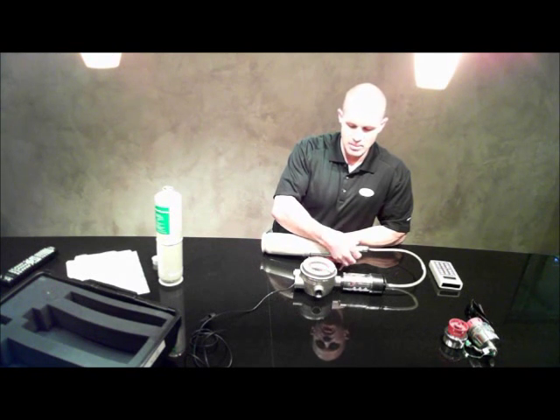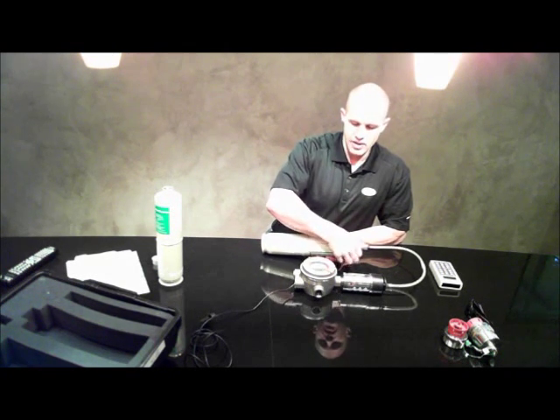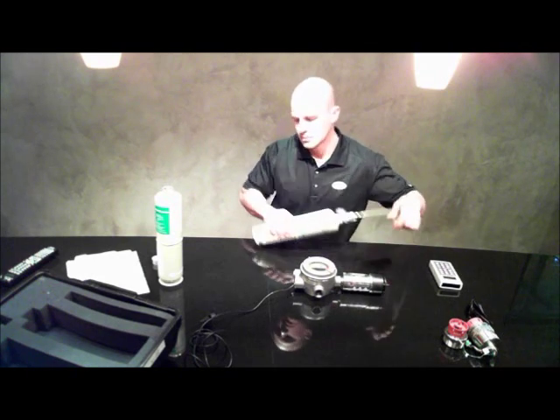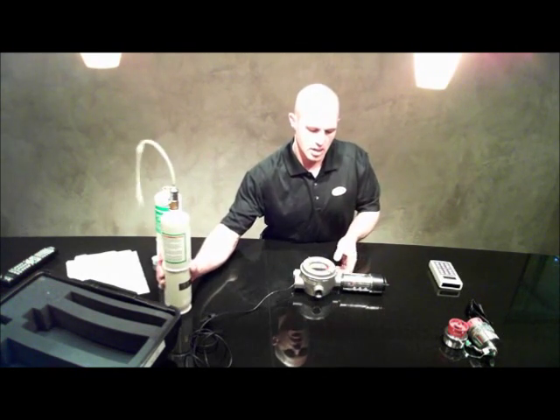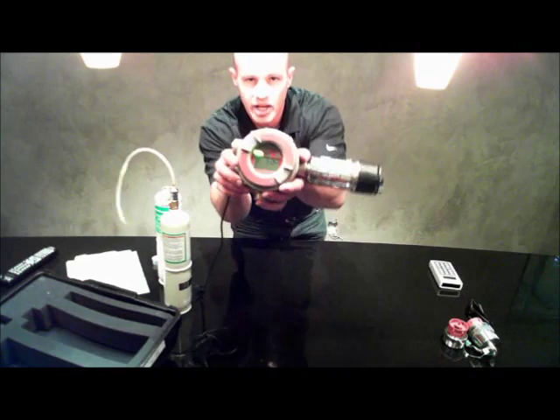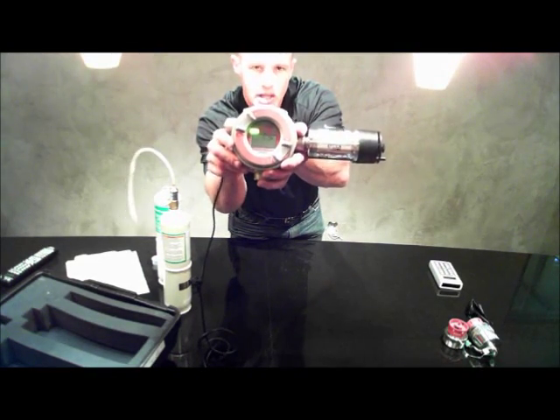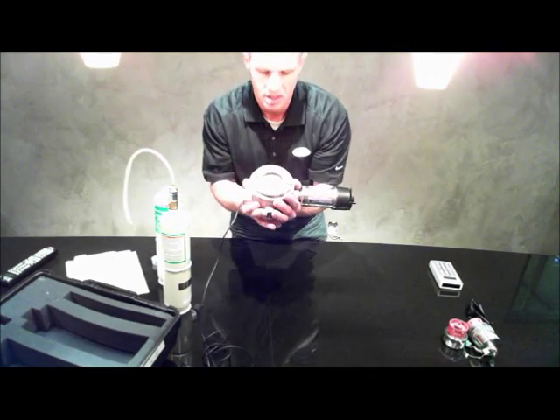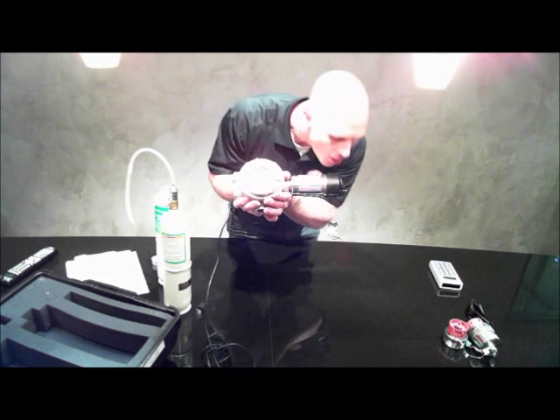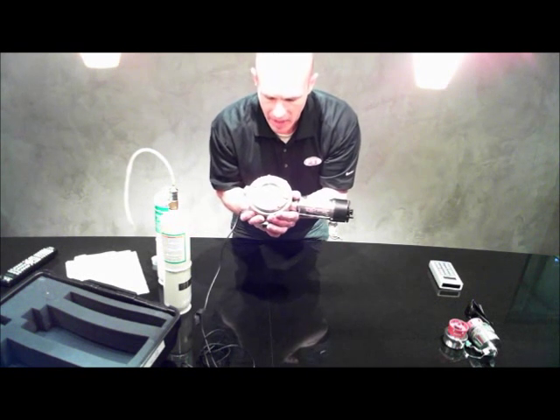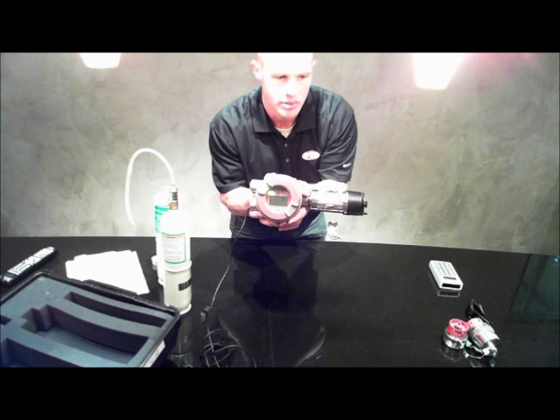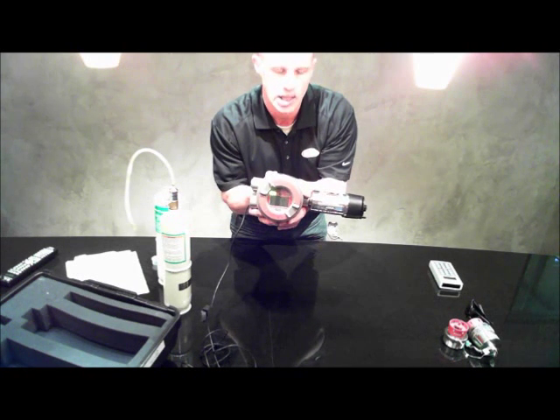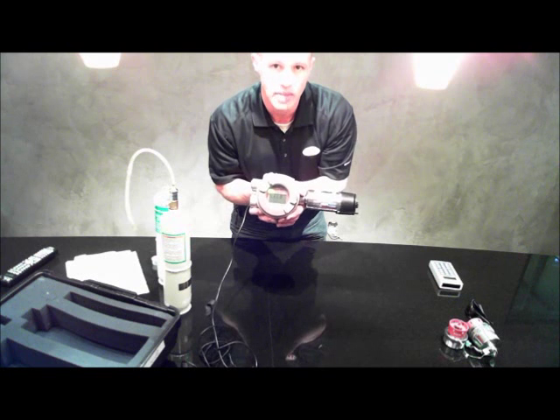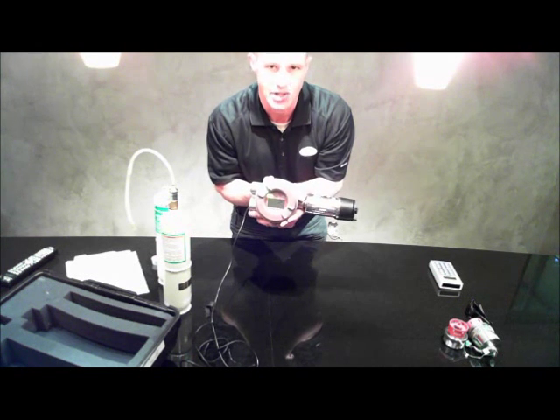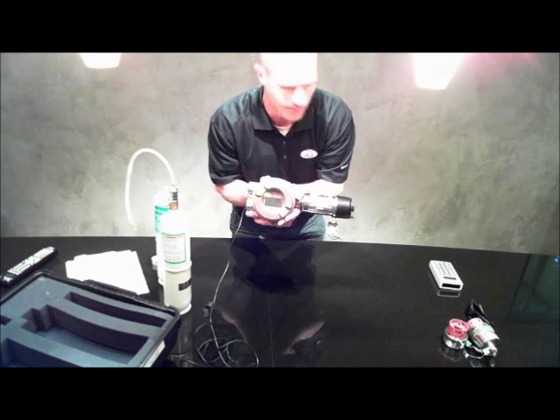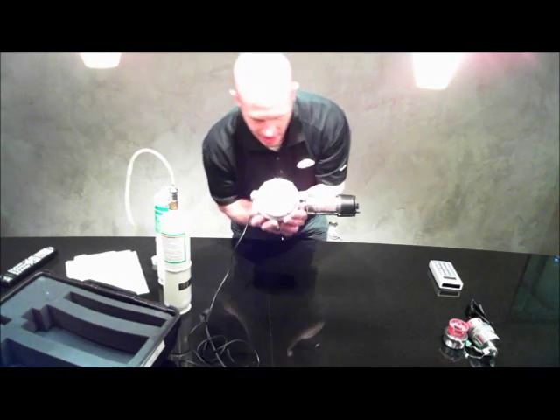It says end, so I can cut the flow off there. Right now it's saying 50%. I've got a normal indication, 50% LEL. That's just because this is a 50% gas. It's dropping down. If I blow that out a bit, you can hopefully see that green LED. You've got about 2 minutes after a calibration before gas exposure will trip an alarm. And it's dropped down to 0.